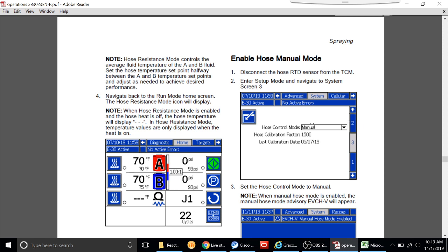Now you see this number right here where it says hose calibration factor. What exactly is a hose calibration factor? So it's the calibration factor that helps the machine determine how much hose we have on here. For example, the value is roughly 330 per 50 feet on a 3/8" hose. So if you have 5 sections, you take 330 times 5, and that's roughly going to be that hose calibration factor.